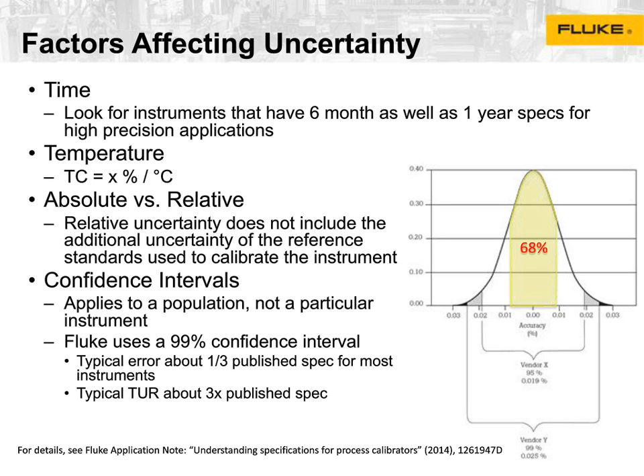Temperature is a factor. I'm hoping most of you have heard of temperature correction. I'm not going to go into a ton of detail about it here, but basically gauges are specified around 23 degrees Celsius, plus or minus either 5 or 3, depending on the manufacturer. And then once you get outside that range, you have to apply a temperature correction. That temperature correction can be pretty significant, and especially in oil and gas, where we see people using gauges in extreme weather, so up on the North Slope or down in the Gulf, where the temperature can get pretty hot. The temperature correction is a non-trivial factor and really needs to be accounted for. I have a bunch of detailed calculations in the application note that I've listed here at the bottom of the page.